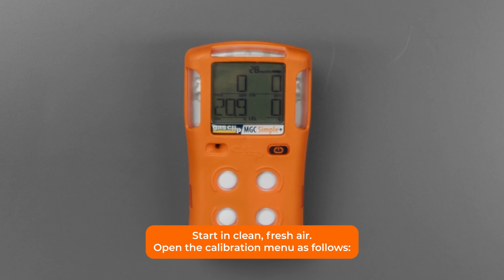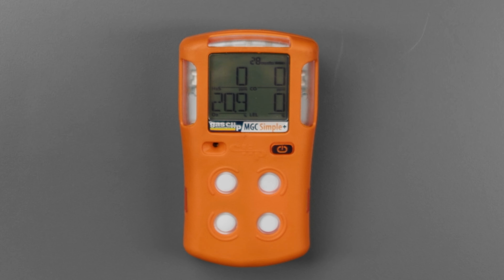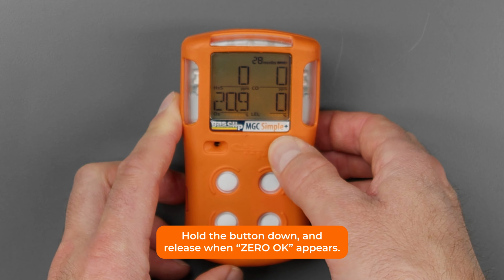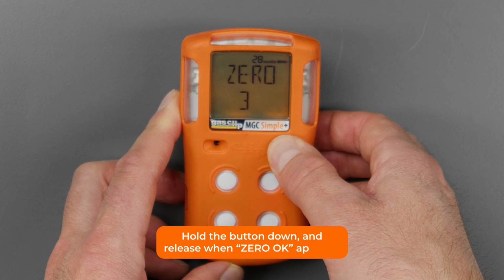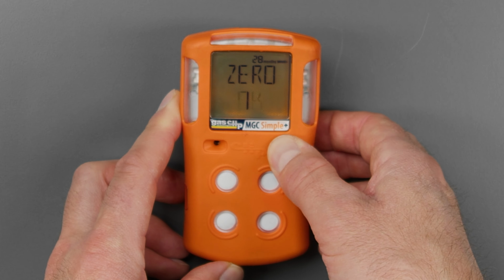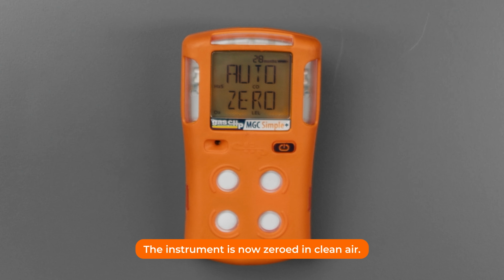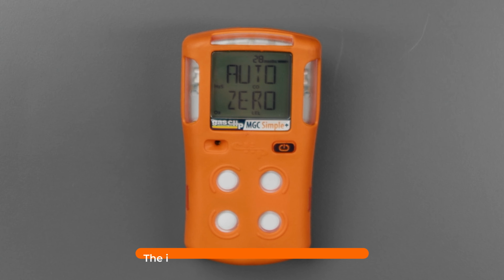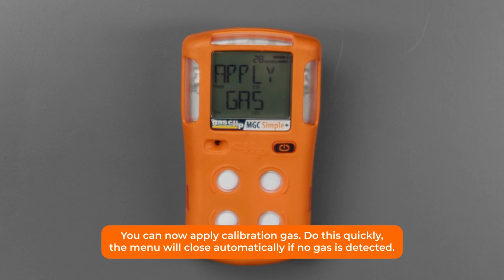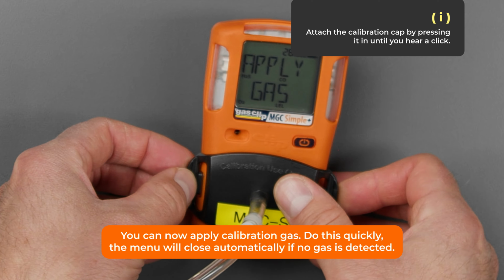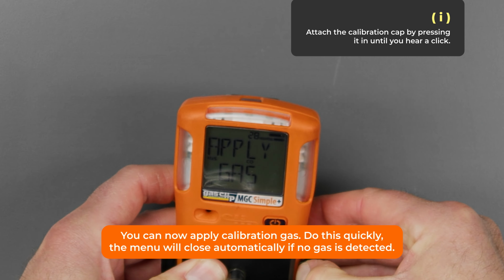Open the calibration menu as follows. Hold the button down and release when ZERO OK appears. The instrument is now zeroed in clean air. You can now apply calibration gas. Do this quickly. The menu will close automatically if no gas is detected.